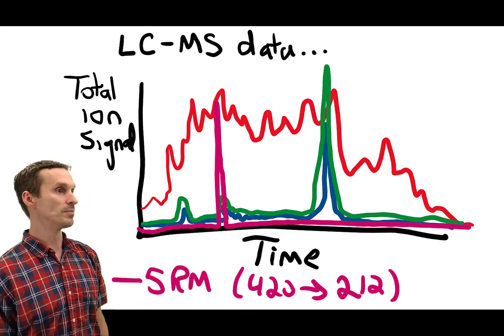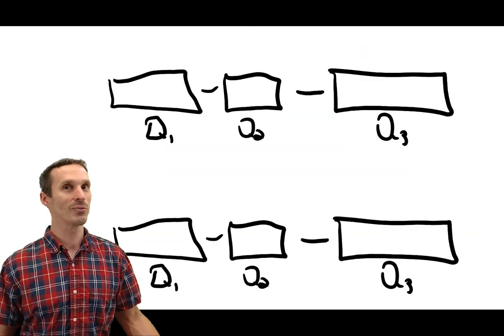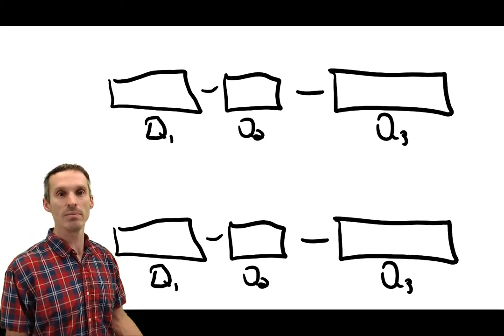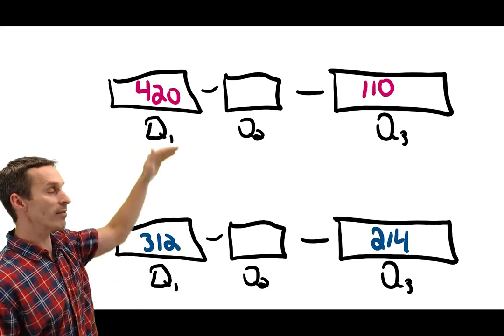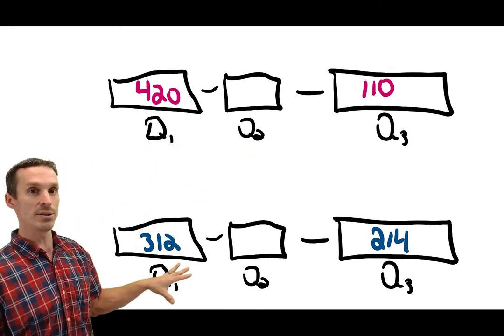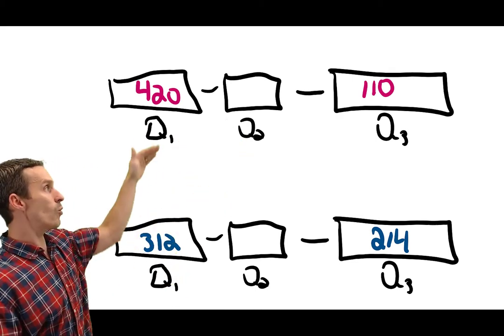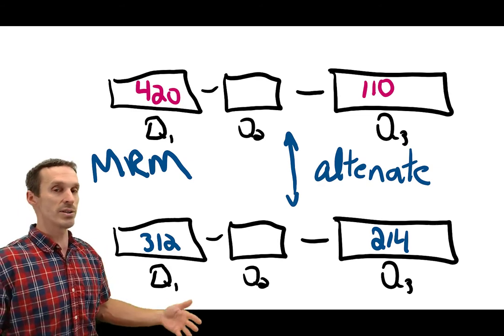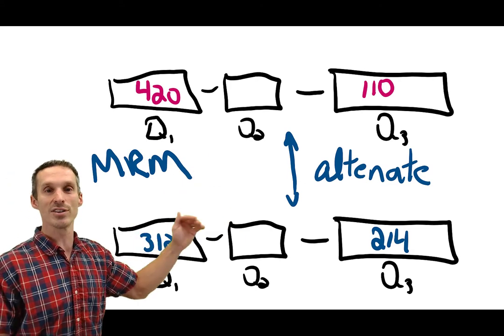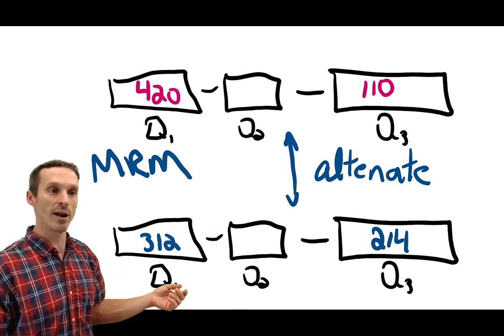This is what we would call selected reaction monitoring, and we always label it with the parent mass and the product mass. So this 420 to 212, we call that an MS-MS transition. Finally, of course, if we can do it with one mass, we could do it with others. Quadrupoles and triple quadrupoles operate extremely quickly. If I was interested in both compounds, I could select different masses in all instances, and what I can do is just quickly oscillate between top and bottom. You could do this every second—you could do 10 different transitions every second.